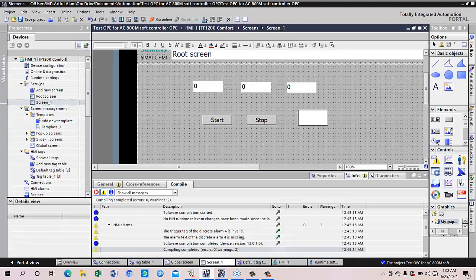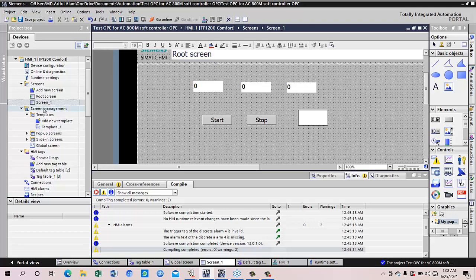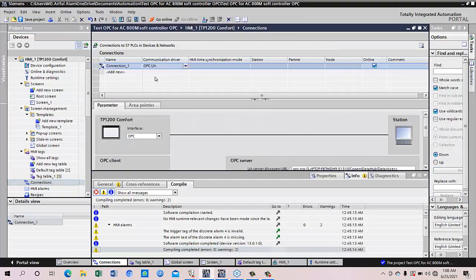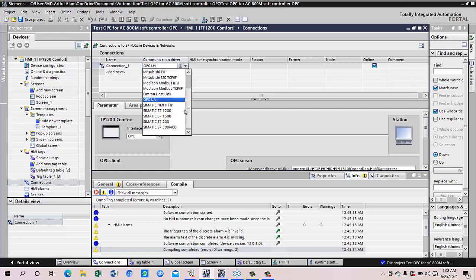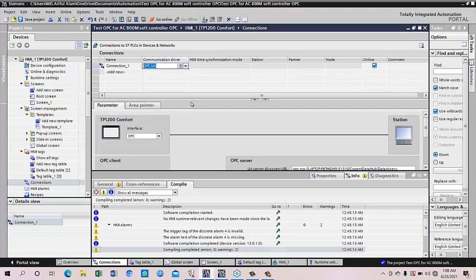Now the problem is we are using TIA Portal 13 and HMI TP 1200. So if we go for the tag connection, we can see the connection only supports OPC UA among many other things, but it cannot connect to ABB. So we have to connect OPC UA to the OPC server of the AC 800M for ABB, but AC 800M OPC server is OPC DA.